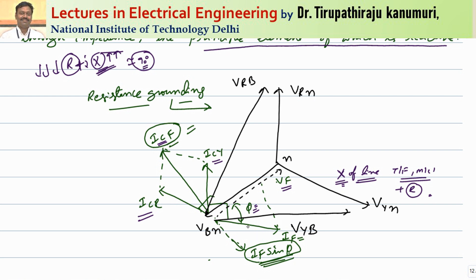The combination r + jx decides the value of angle phi, which will always be less than 90 degrees. Some component of IF — equal to IF sin phi — will be 90 degrees lagging behind the voltage, opposing the capacitor currents. If IF sin phi exactly equals ICF, the resultant currents become zero, cancelling the capacitor currents and completely eliminating the phenomenon of arcing grounds.